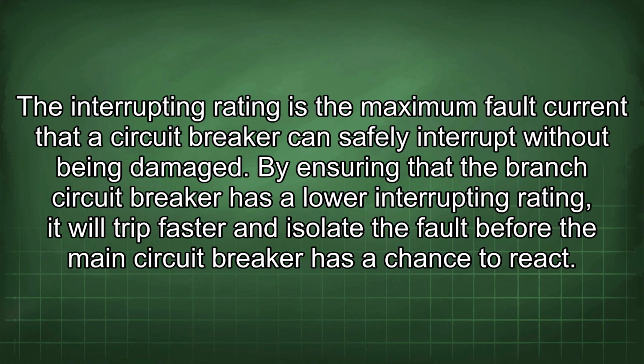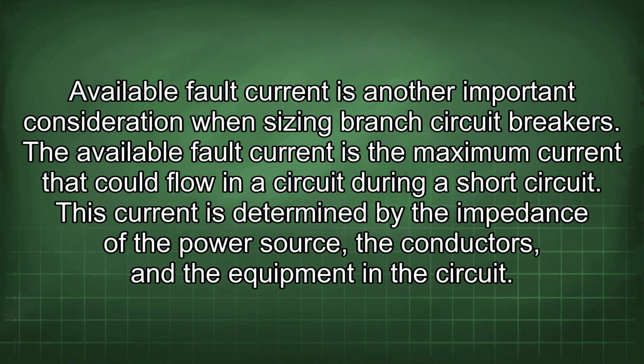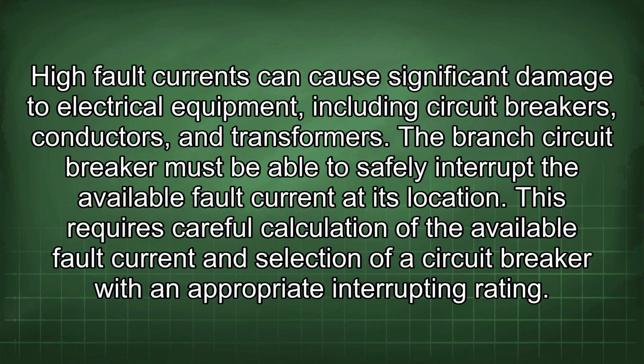By ensuring that the branch circuit breaker has a lower interrupting rating, it will trip faster and isolate the fault before the main circuit breaker has a chance to react. Available fault current is another important consideration when sizing branch circuit breakers. The available fault current is the maximum current that could flow in a circuit during a short circuit. This current is determined by the impedance of the power source, the conductors, and the equipment in the circuit. High fault currents can cause significant damage to electrical equipment, including circuit breakers, conductors, and transformers.